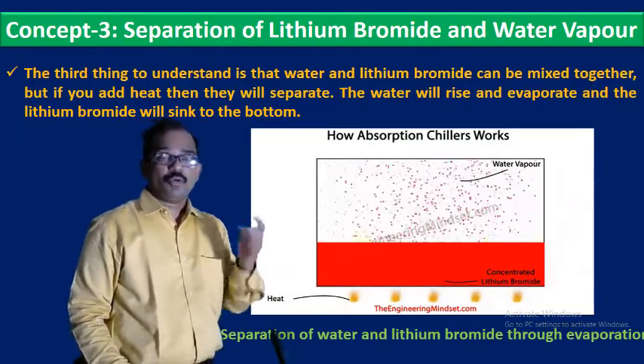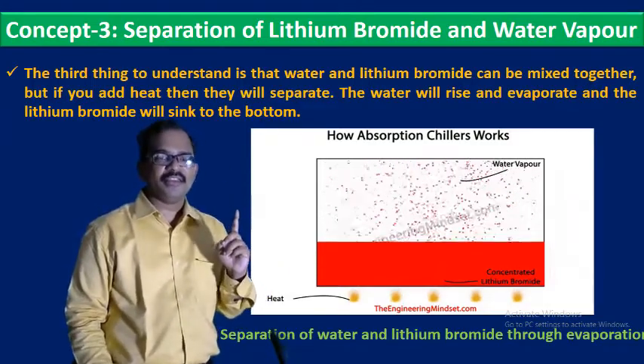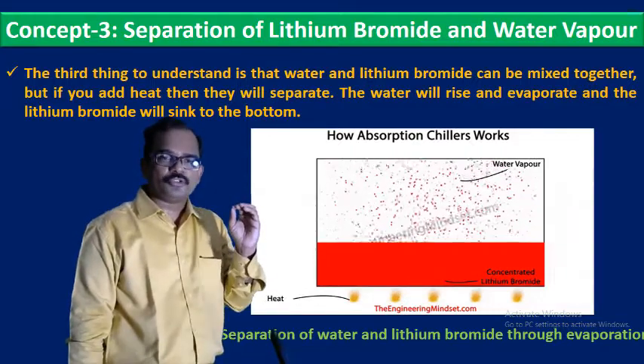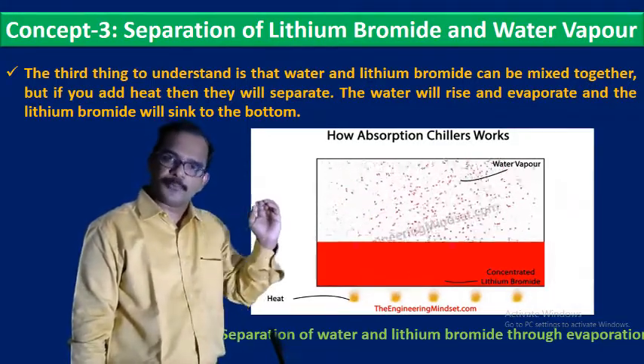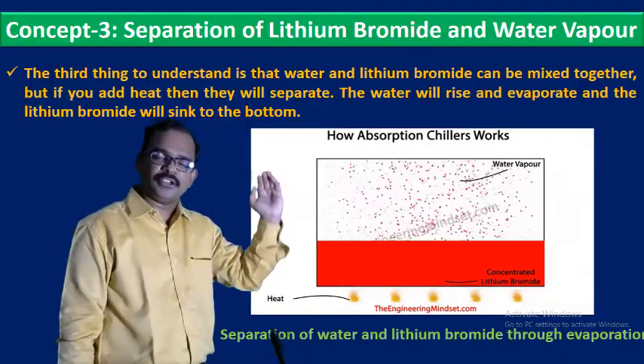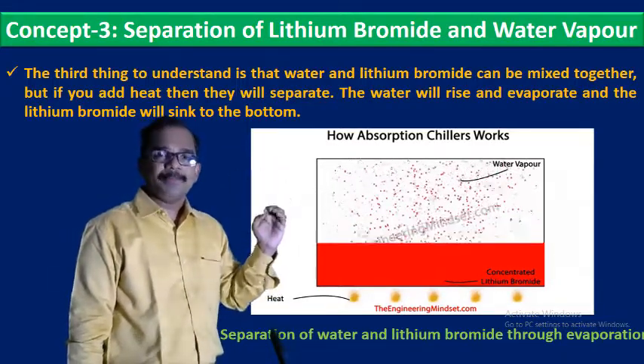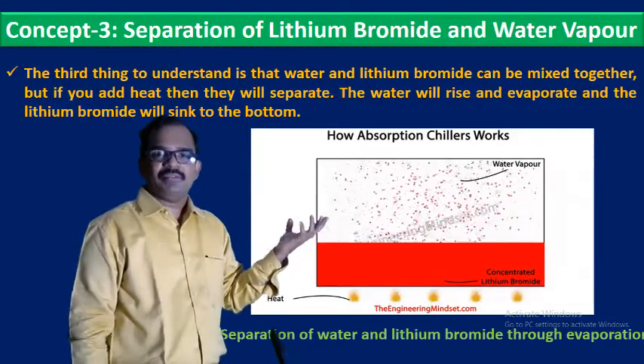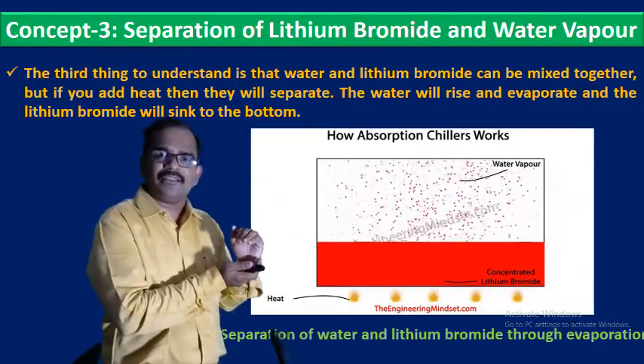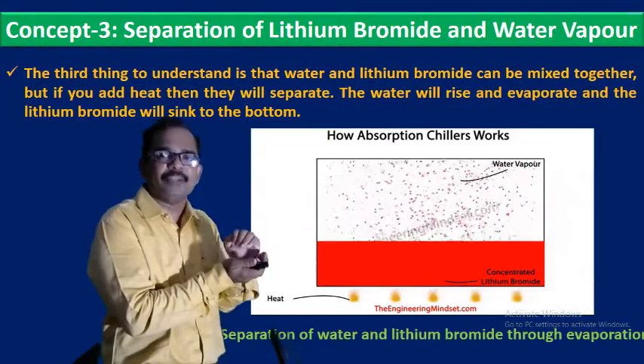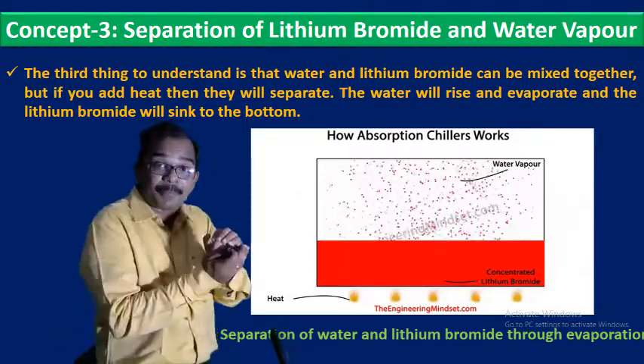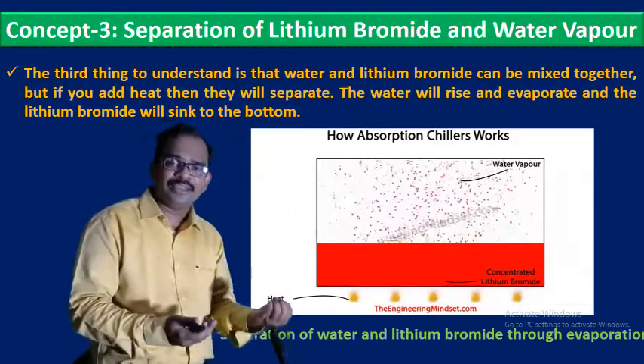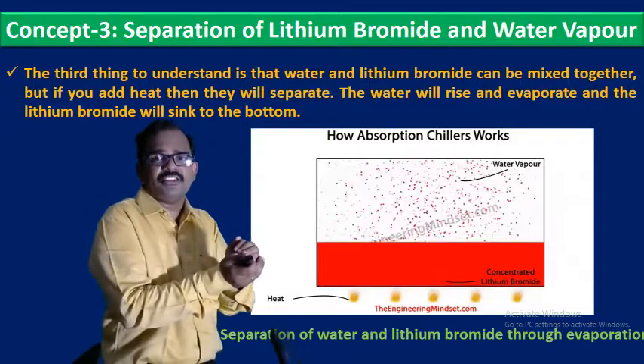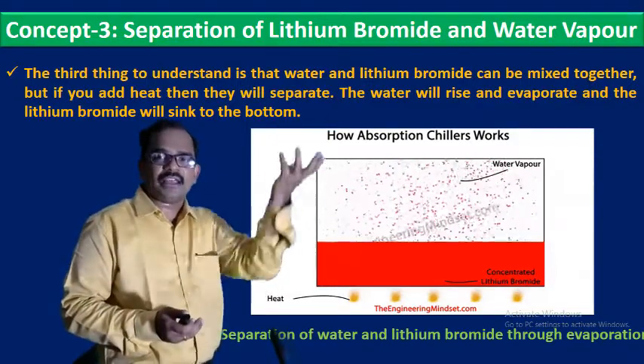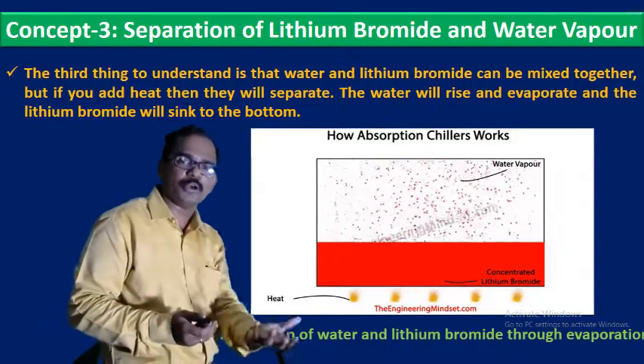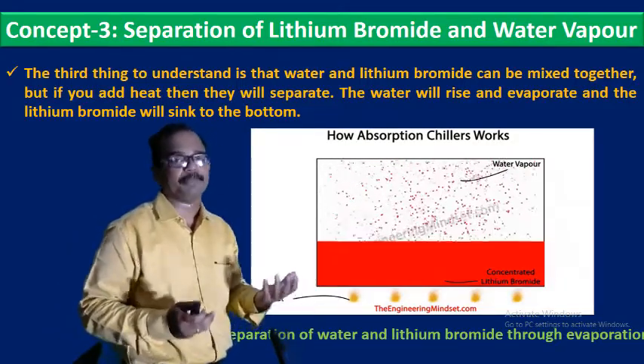Right? Now what is the first concept? The first concept is that the boiling point of water is directly proportional to the pressure. As the pressure decreases, the boiling point decreases. As the pressure increases, the boiling point also increases. The second concept is the mixing of lithium bromide and water vapor. When they both come in contact with each other, because lithium bromide is a salt, it has strong affinity towards the water vapor and they will mix together perfectly. And the third concept is the separation of lithium bromide and water vapor. When you heat the mixed solution of lithium bromide and water, the water will get evaporated and move upwards. Lithium bromide settles at the bottom of the container in which it was kept.